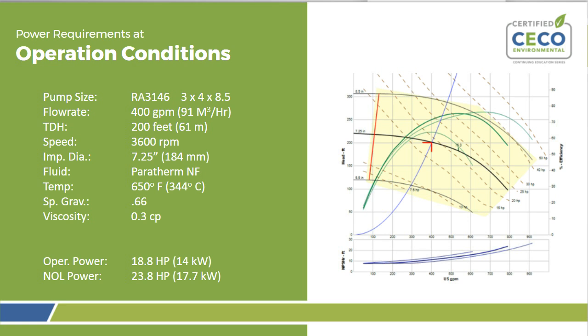So when the engineer goes in and looks at his conditions, he's going to select his pump and his motor and everything else, and all the switchgear that goes along with that. This is his application and this is what he's going to look at. For this application, if you examine the curve, the operating power to run this pump is going to be about 18.8 horsepower. And if you go to non-overloading power, which is basically the power at the end of the curve, you get about 23.8. So if you had a 25 horsepower motor on this application, you should be able to cover the operating conditions without a problem.